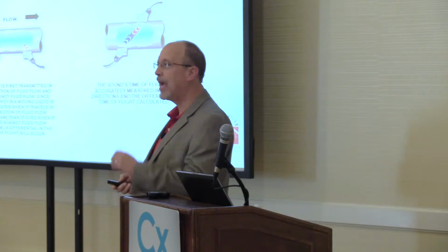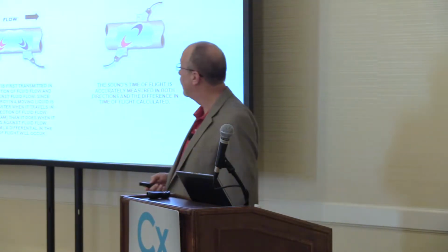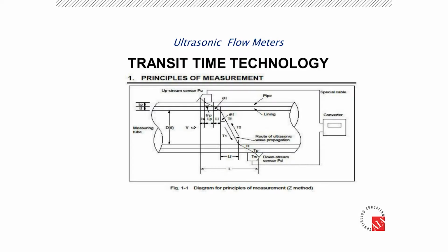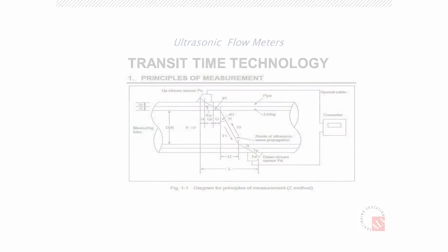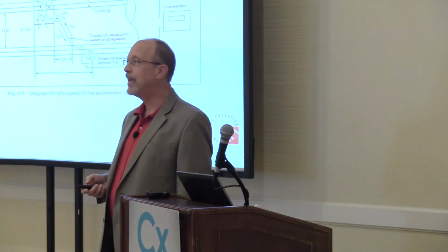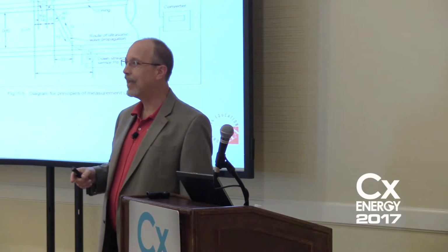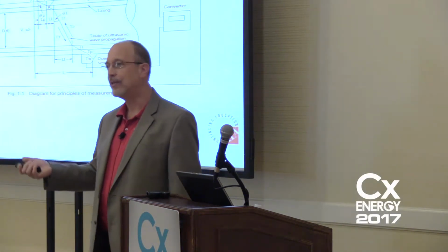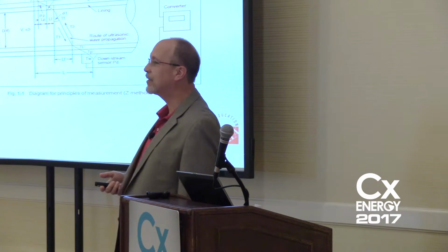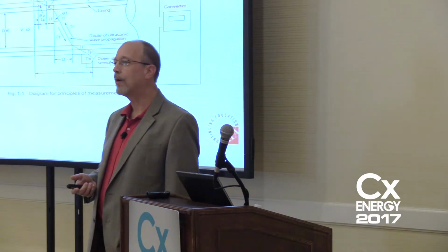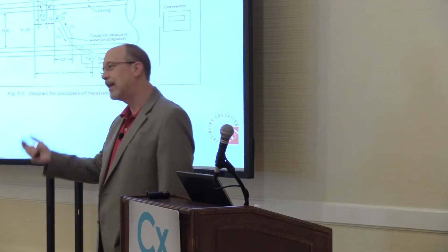Now the math of this equation is the same basic math that it has been for 50 years. So as we look at this cutaway from the inside of the pipe, this is a transducer, this is a transducer. And the novelty of a transit time flow meter is that it's just a big math equation. That's all it is. In the old days, you had to do the math. Today, it kind of does it for you. So life is easier. You don't have to dial in the specific sound speed of 32-degree water with 70% glycol. The meter does it for you.